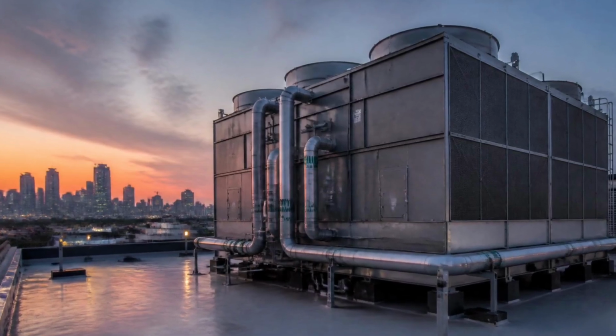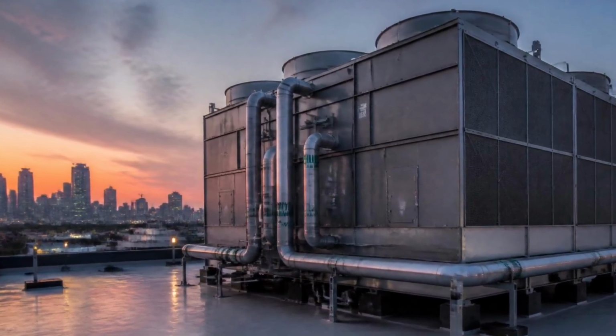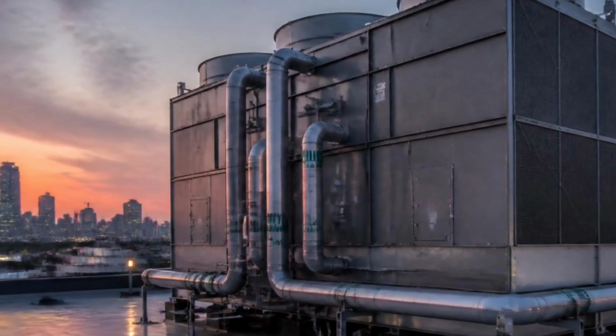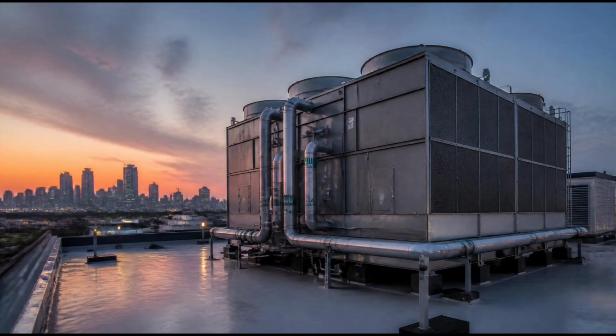Heat exchangers move heat efficiently from one place to another. At various points in the water loops, heat exchangers allow energy to pass between fluids without the fluids themselves mixing. A plate heat exchanger, for example, passes two fluids on opposite sides of a series of thin metal plates. Heat flows through the plates from the warmer fluid to the cooler one, transferring energy with high efficiency. These devices are compact, reliable, and operate with no moving parts of their own, relying entirely on the pumps to keep both fluids in motion.